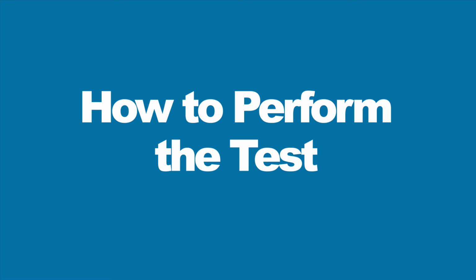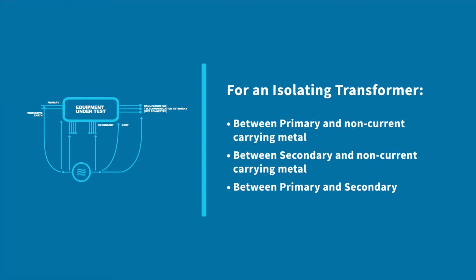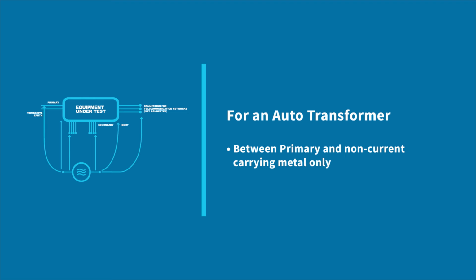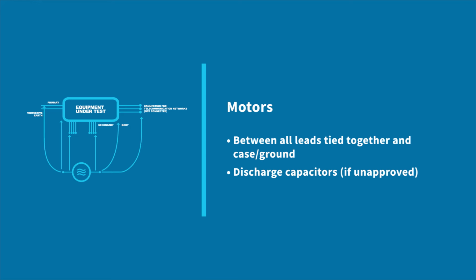How to perform the test? For an isolating transformer, between primary and non-current carrying metal, between secondary and non-current carrying metal, between primary and secondary. For an auto transformer, between primary and non-current carrying metal only. Motors, between all leads tied together and case or ground. Discharge capacitors if unapproved.